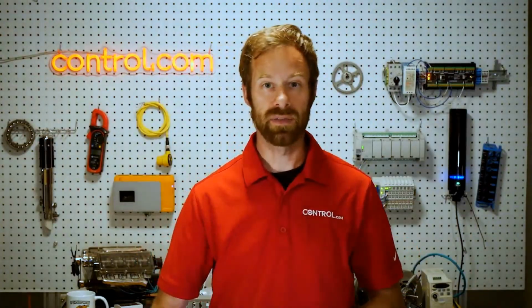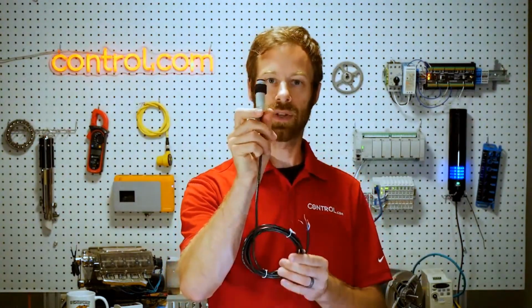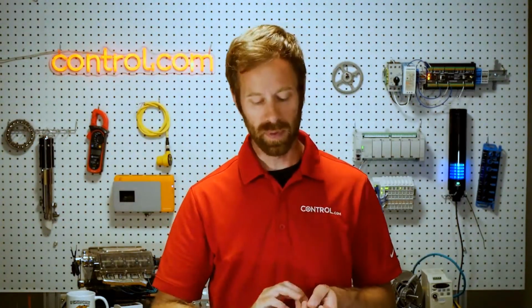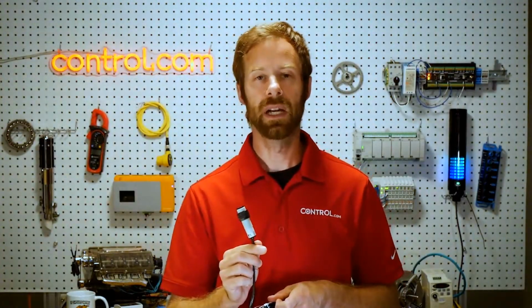Unlike the 2-wire sensors, where until the physical circuit was completed when you push the button, there's no electrical flow, if I have positive and negative supplied to this sensor, I can power semiconductor electrical circuits inside. One of the most common semiconductor ones is an LED. You'd see an LED that would indicate the presence of no object, and it would also indicate the presence of an object. Well, how would it get enough voltage to be able to run that LED if there was no voltage supplied from both a positive and minus source, regardless of whether the object is there or not?